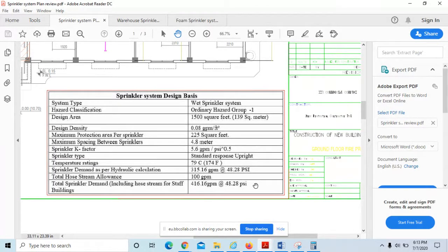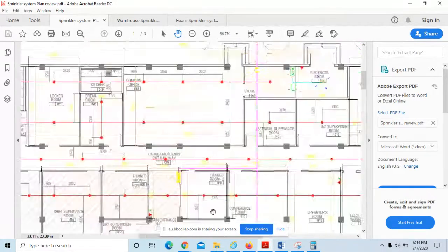Your fire pump can supply this much flow at this much pressure. Now you can select based on the skills we learned in fire pump design, right? How to select the pump performance curve and all of that. No issue with that. But this will never tell what the capacity of the pump is. We just want to make sure of the size of the pump for this application from the data sheet of the fire pump, or if there is an existing fire water network, we want to make a flow test to confirm that at this connection point, this is our demand point.